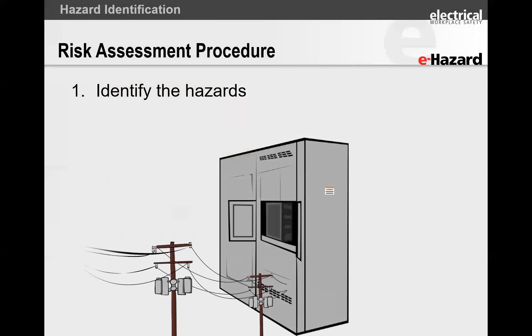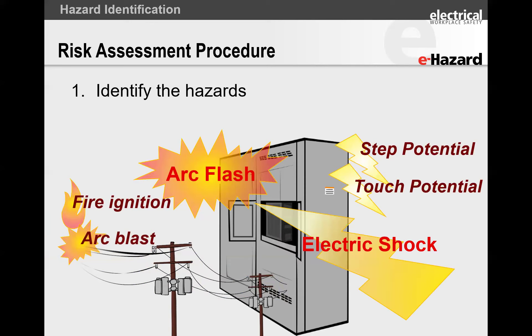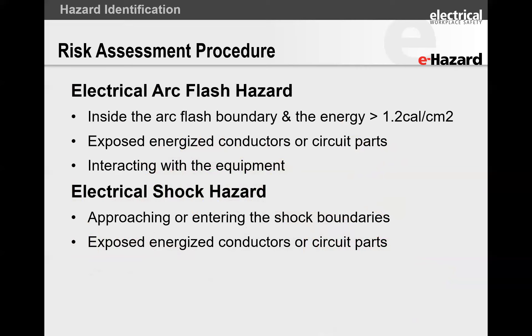Let's start with the back to basics: identifying the hazards. Electrical hazards — how many do we have? There are only two. It is electrical arc flash, and it is electrical shock. Electricity-wise, you are either going to get burned, or you're going to get current through your body. You can get shocked by touching something, or you can get shocked by stepping into an area where the ground voltage creates a current path. Those are the two mediums for electrical shock. Then you have arc flash, where something goes boom — you get that blast, the thermal component, and the pressure component.